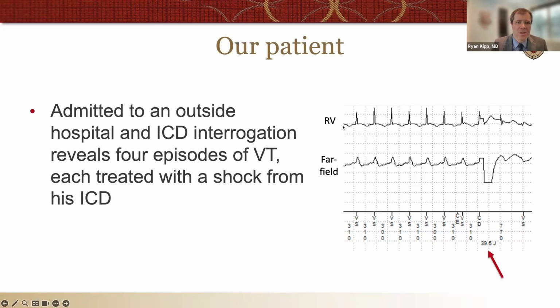This is how the electric signals look in the heart from the tip of the ICD lead. This helps the ICD determine the heart rate. You can see here that the defibrillator is recognizing each of those little spikes as a ventricular beat, saying V sense, or ventricular sense. This time here is the milliseconds between each heartbeat, which tells you how fast the device thinks the heart rate's going. At 310 or 300 milliseconds, that's a heart rate around 190 or 195 beats a minute.